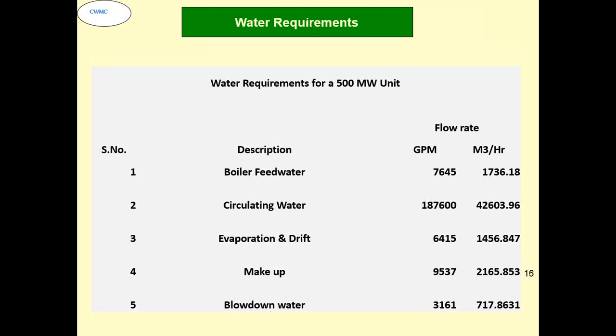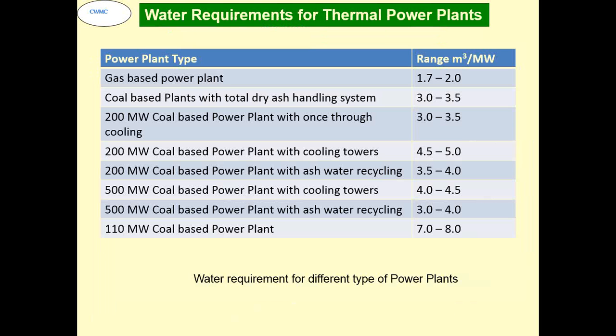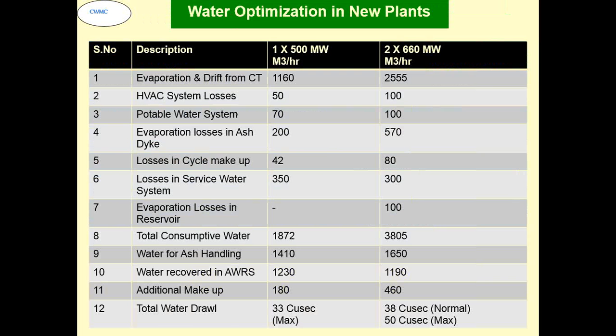This is the quantum that you see from the uses in different sectors. This is sort of per capita or per megawatt, what is the water consumption for different kinds of power plant. This is something which was optimized recently, and you see about 50 cusec of water will be available for 2 into 660 megawatt units, whereas for 500 megawatt till now it was about 33 cusec. So you can see, whatever optimization was possible, a lot of things have already been taken care of and optimization has been done in terms of water utilization.